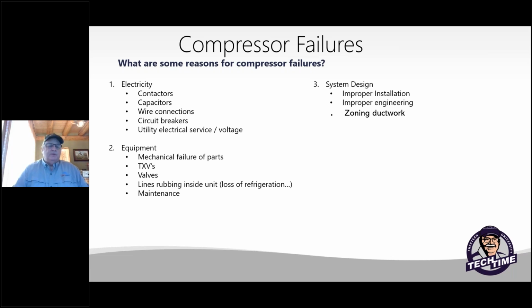We also know, obviously, you can have mechanical failure parts. Expansion valves go bad, reversing valves could go bad, solenoid valves could go bad, causing these compressors to not run in their operating parameters, creating more problems. Refrigerant lines, loss of refrigerant, the slow death of a compressor can happen as well. So always make sure that your lines are not touching or rubbing. Capillary lines aren't rubbing on electrical wires inside as well.